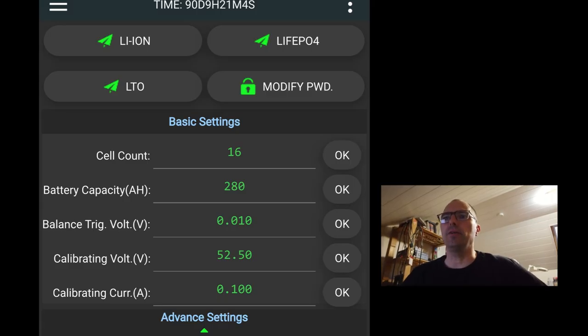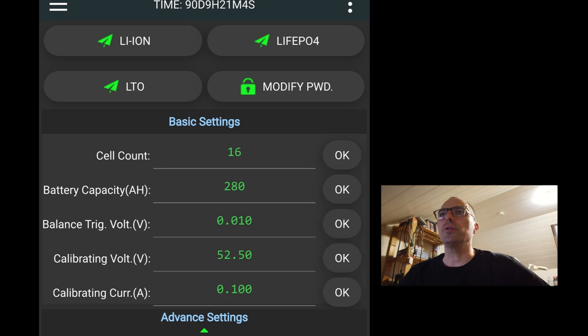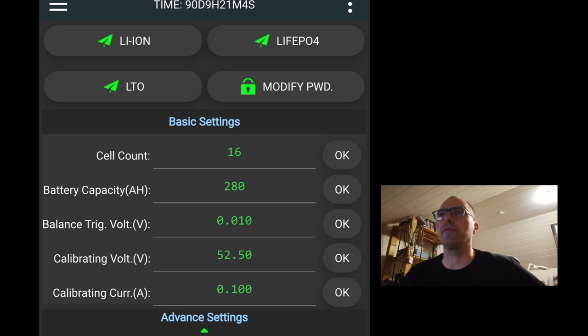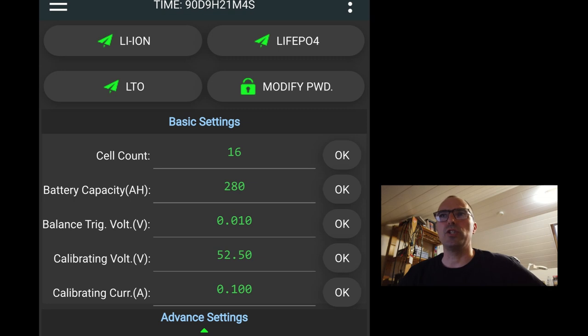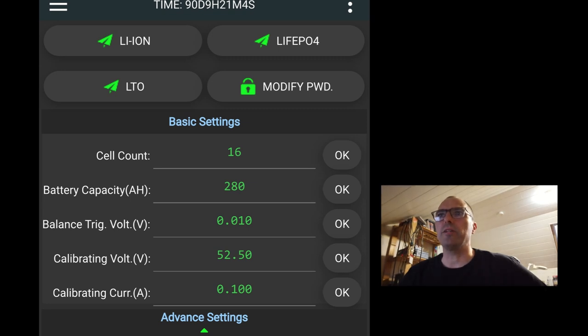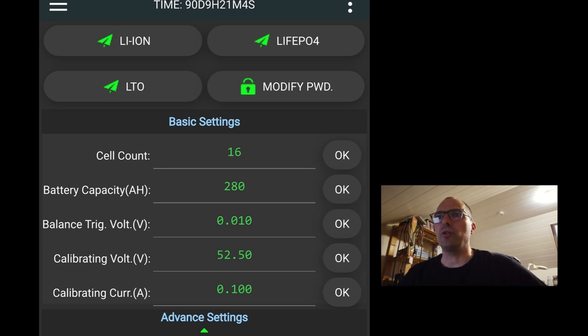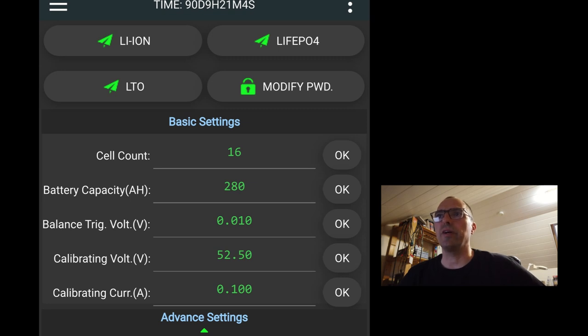Let's dive into the advanced settings menu. Important to know if you want to change any setting here, you have to enter the password. The standard password is 123456. At the top, you can choose the technology. Lithium-ion, LiFePO4, LTO. It's good to know if you change the settings, it will automatically fill all the settings with the standard parameters of that technology. So if you programmed everything for LiFePO4 and you just want to have a look for the lithium-ion settings, know that all settings will be overwritten and you have to redo the programming. So be very cautious about this thing.